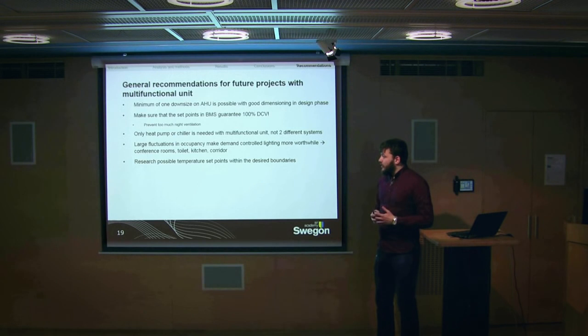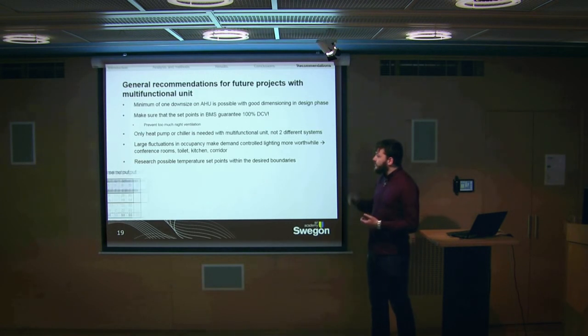It's also good to research possible temperature set points for the desired boundaries, meaning what kind of indoor climate you want. If we had gone for class 2, with a PPD lower than 10%, the temperature set points could have been further apart, saving more energy but not giving the best possible indoor climate. So within the frame set for the indoor climate, it's good to investigate these temperature set points to save more energy while still guaranteeing the desired, hopefully best possible, indoor climate.